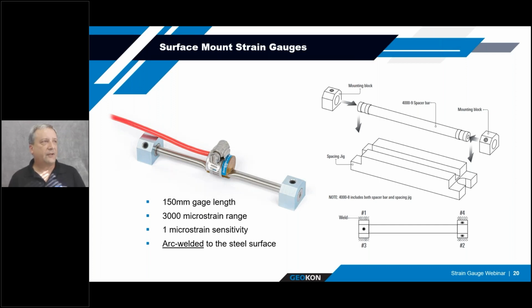To do the installations, because this is basically called an arc weldable strain gauge, and the reason it's called that is because that's how it's typically adhered to a surface, and it's typically mounted on a steel element. To do that, you would basically have these end blocks, and you wouldn't install the vibrating wire assembly and tube yet, but you would use what's called a spacer bar and a spacer jig. With that spacer bar, that helps align the mounting blocks on either end parallel to each other and at the right distance. And so you secure the mounting blocks to that spacer bar, hold it up against your structural element, and then using an arc welding method, apply a weld along the top and bottom of each of these end blocks. You don't want to go around the end, because sometimes those welds will get too thick and block passage, so you couldn't get the spacer bar out and not get the instrument installed either.